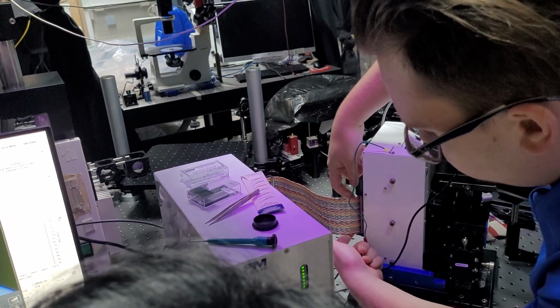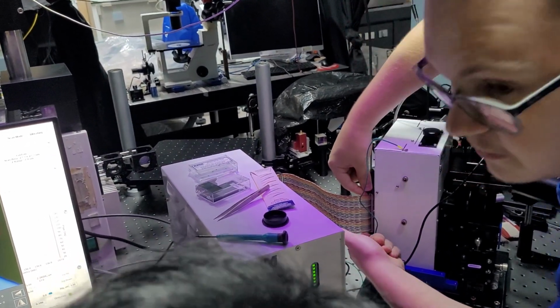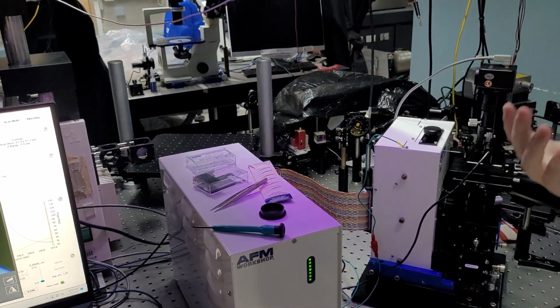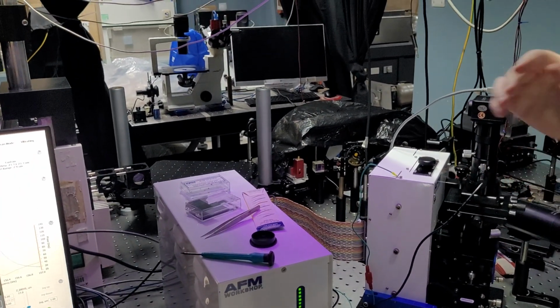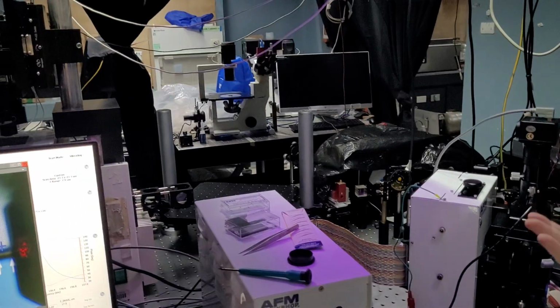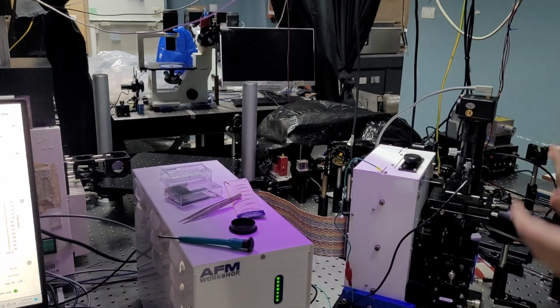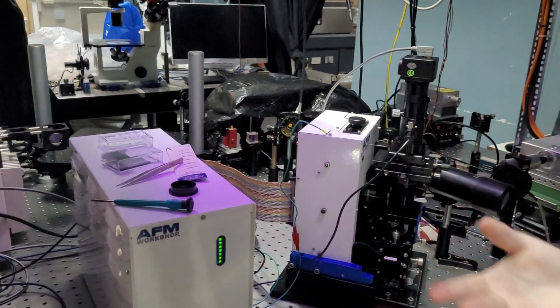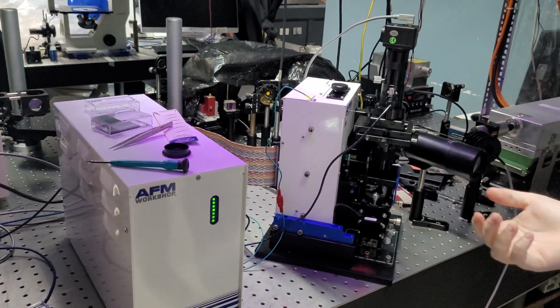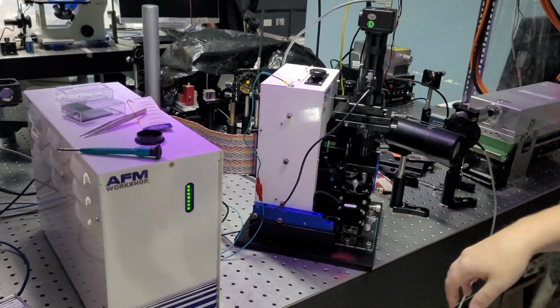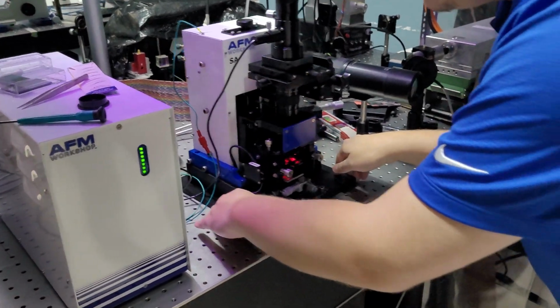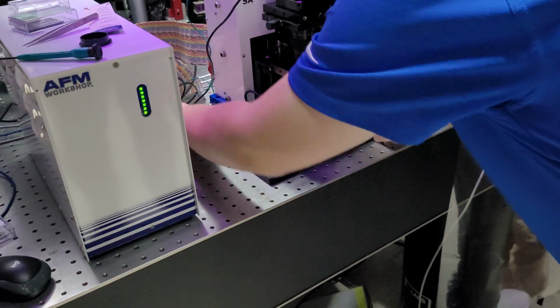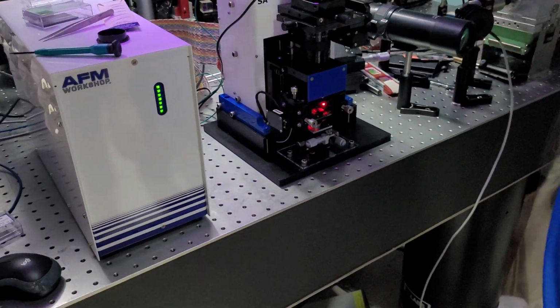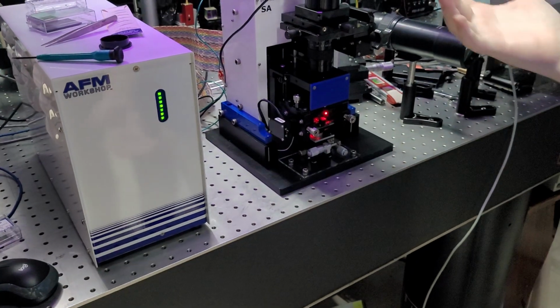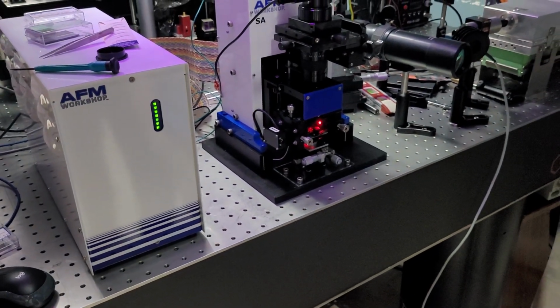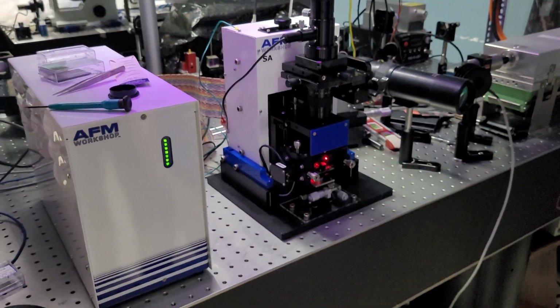the rainbow cable should be pushed in enough to where these clips are clipped into place. 95% of the calls that we get from customers are they move the AFM, those clips aren't all the way in place, and it's like weird things, like their motor's not working, or their range check isn't working, something like that. And so I just have to sit down and say, okay, we'll clip it in. But just to kind of visualize that can be a little bit of a headache in the future if you do move it. As far as cables, that should be it.